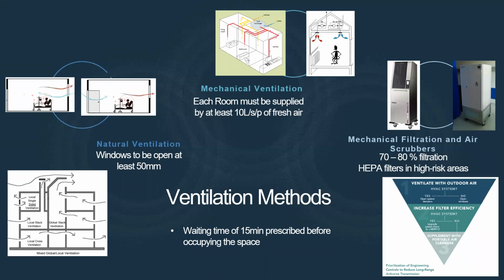Now this is typically where you have rooms on the outskirts of the building envelope, where you actually have windows and doors that you could open to give you this. You do have certain instances where a functional area or ward or ICU is situated more in the core of the building, and in an instance like that, you would then typically have better filtration systems and air scrubbers to alleviate this risk. So you still have circulation of air with a certain quantity of fresh air, but you cannot satisfy the 10 liters per second because it's in the core of the building.